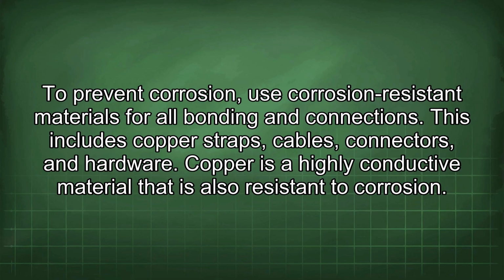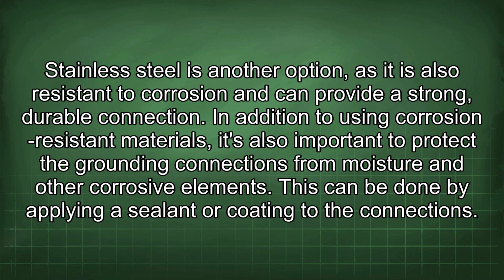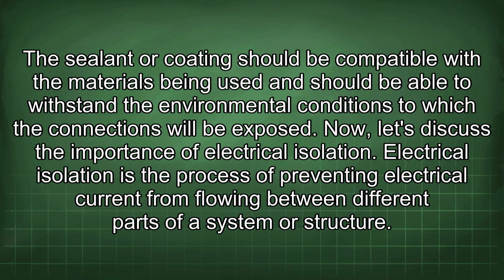To prevent corrosion, use corrosion-resistant materials for all bonding and connections. This includes copper straps, cables, connectors, and hardware. Copper is a highly conductive material that is also resistant to corrosion. Stainless steel is another option, as it is also resistant to corrosion and can provide a strong, durable connection. In addition to using corrosion-resistant materials, it's also important to protect the grounding connections from moisture and other corrosive elements. This can be done by applying a sealant or coating to the connections. The sealant or coating should be compatible with the materials being used and should be able to withstand the environmental conditions to which the connections will be exposed.